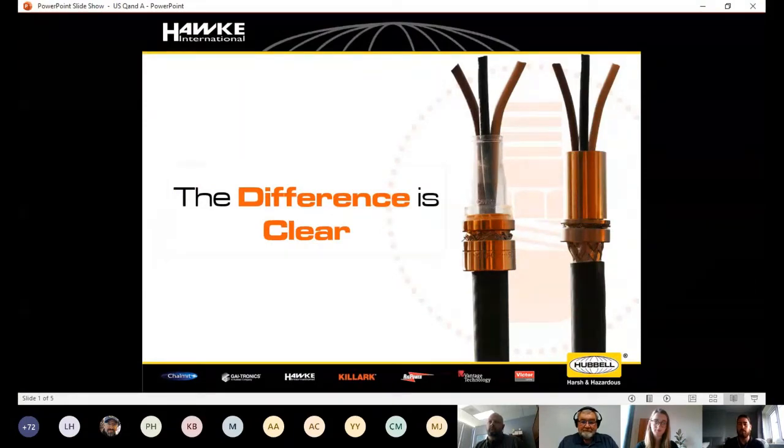That would give you a flame path. That's a traditional way that North America would see cable glands with compound chambers. But we, manufacturing in the UK and being a global supplier of cable glands, saw the benefits of being able to offer something with inspectability. And our previous design, before we moved on to this generation of cable glands, which we switched over to in July 2019, had a removable compound chamber that was made of a Santoprene plastic material.